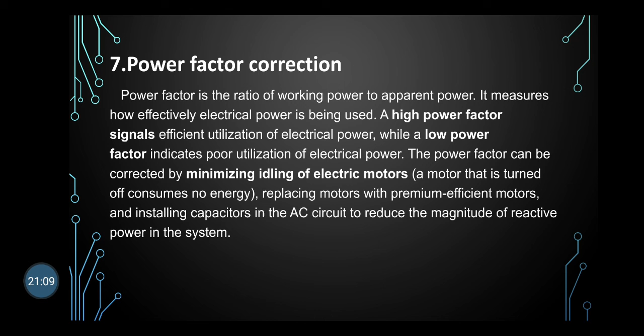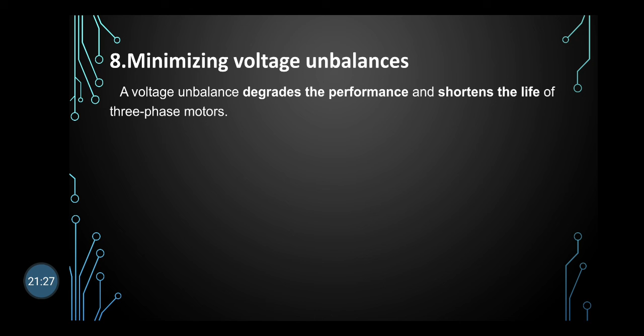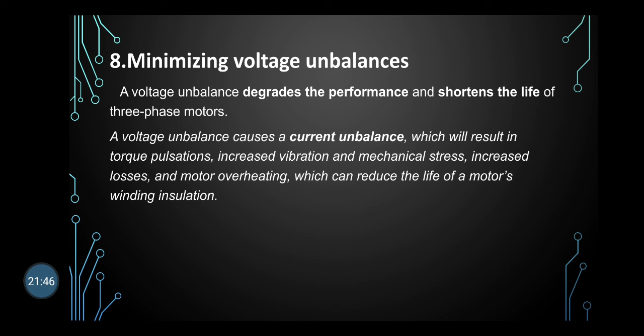Now the eighth one is minimizing voltage unbalances. A voltage unbalance degrades the performance and shortens the life of three-phase induction motors. The voltage unbalance causes current unbalances, which result in torque pulsations, increased vibrations and mechanical stresses, increased losses, and motor overheating, which can reduce the life of the motor winding insulation.